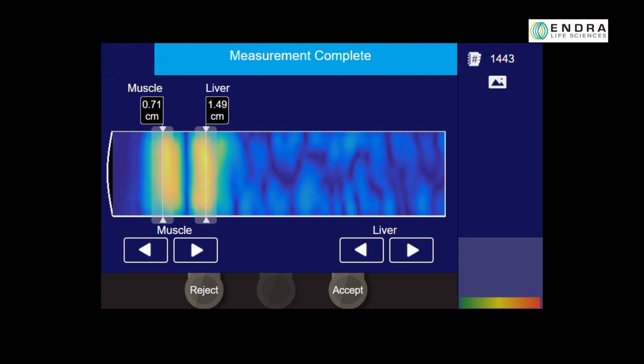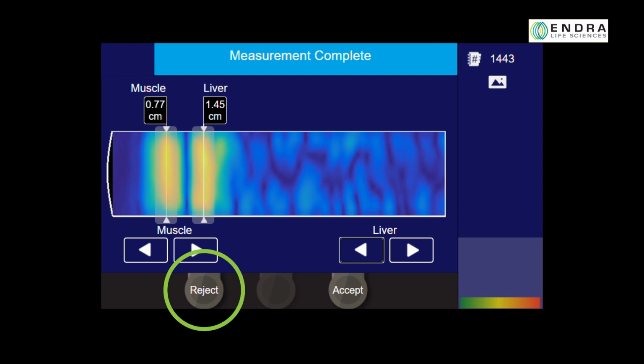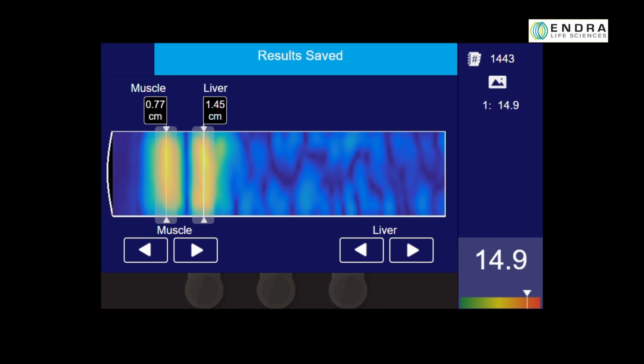When the scan is completed, a graphic is displayed that represents the measured thermoacoustic signal. Ensure that the boundary definitions align with the signals from the muscle and liver, and readjust the boundaries if necessary. If the two signals are not clearly defined, press Reject to perform a new scan. Press Accept to generate numerical data.